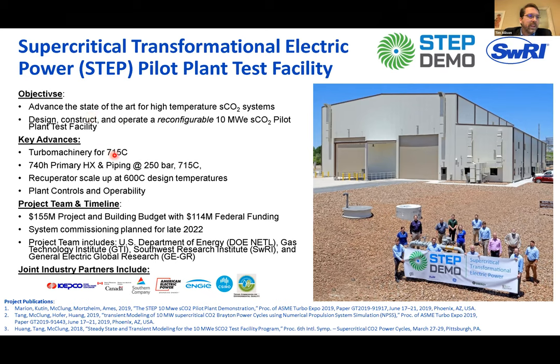We're targeting 715 Celsius turbine inlet temperatures, which is key towards hitting the efficiency metrics. Some of the primary equipment there are piping and heat exchangers that operate up to that temperature, so those are made out of new or emerging nickel alloys like Inconel 740H, and we are bringing up the supply chain for many of those. Our recuperators go up to about 600 degrees Celsius.